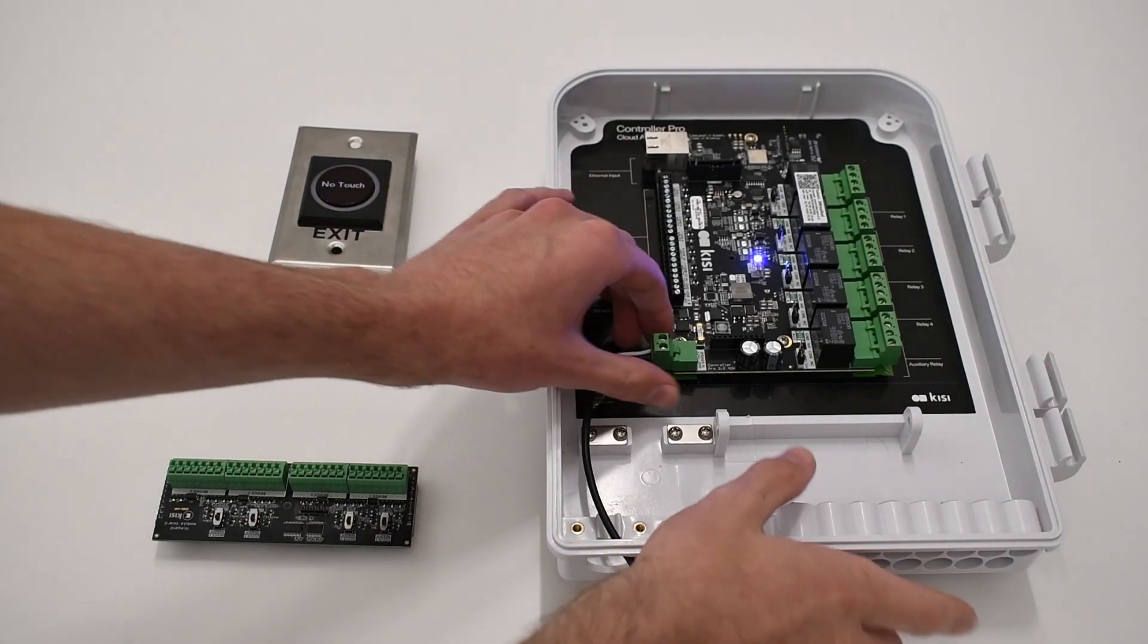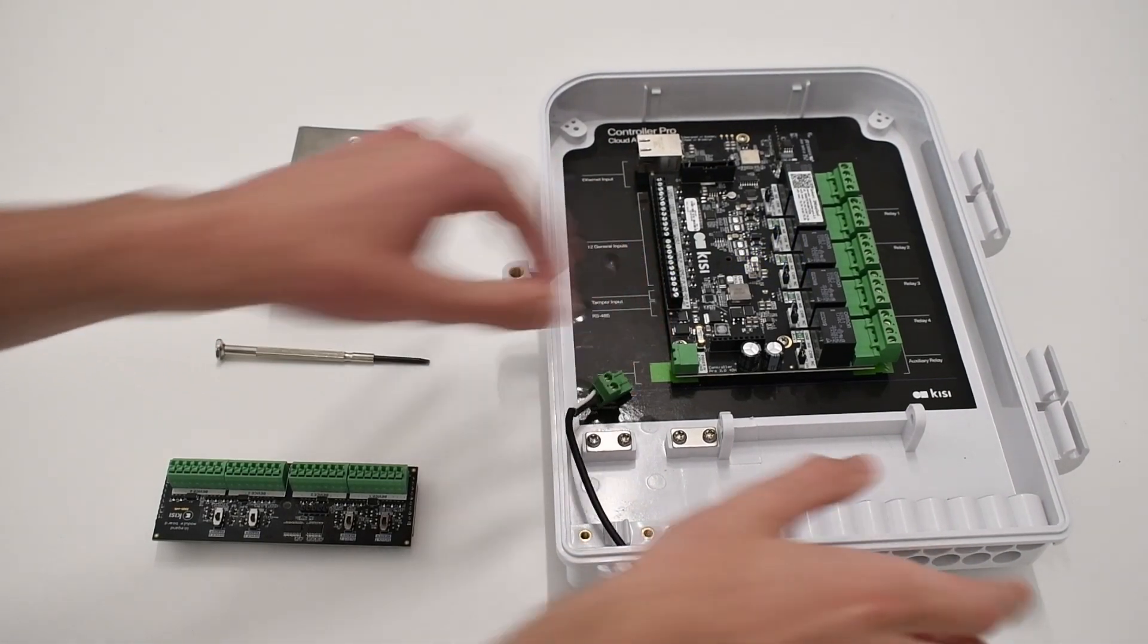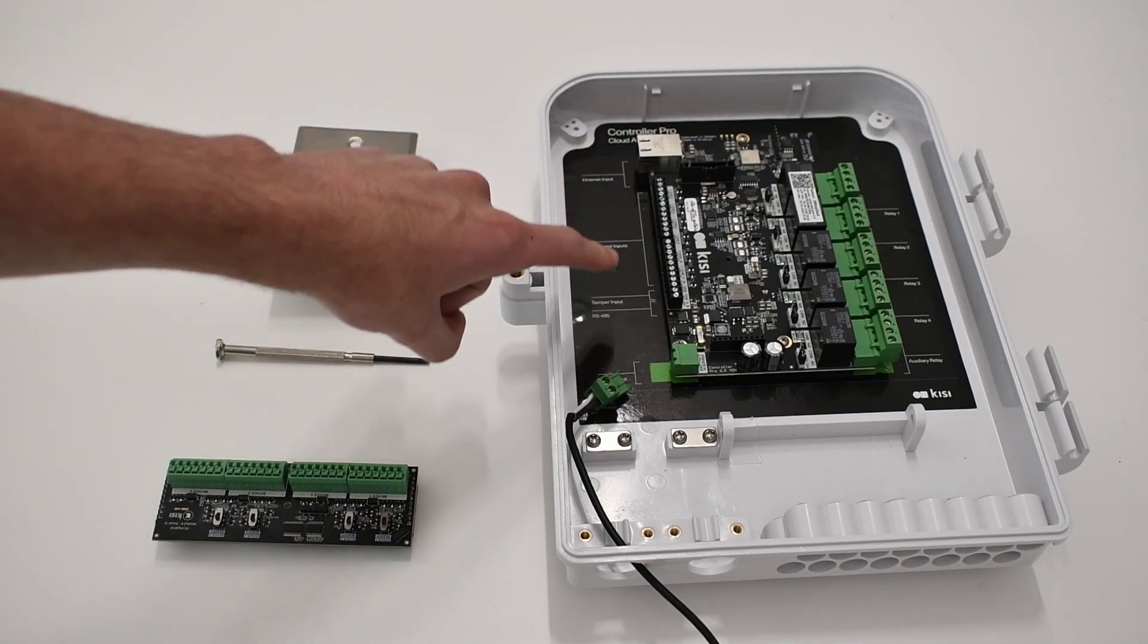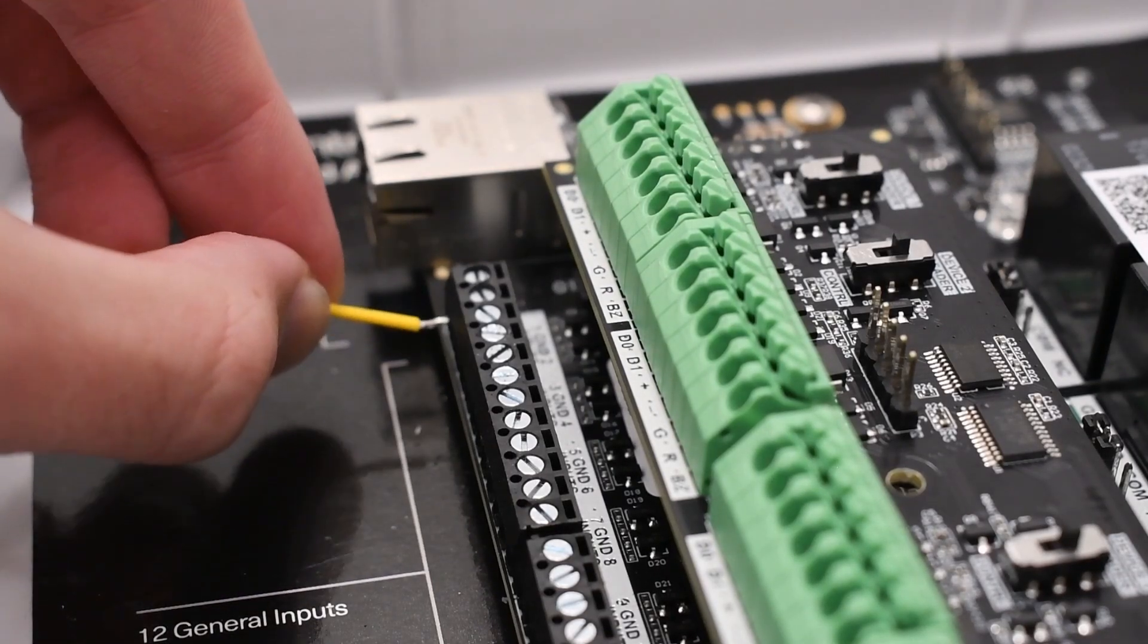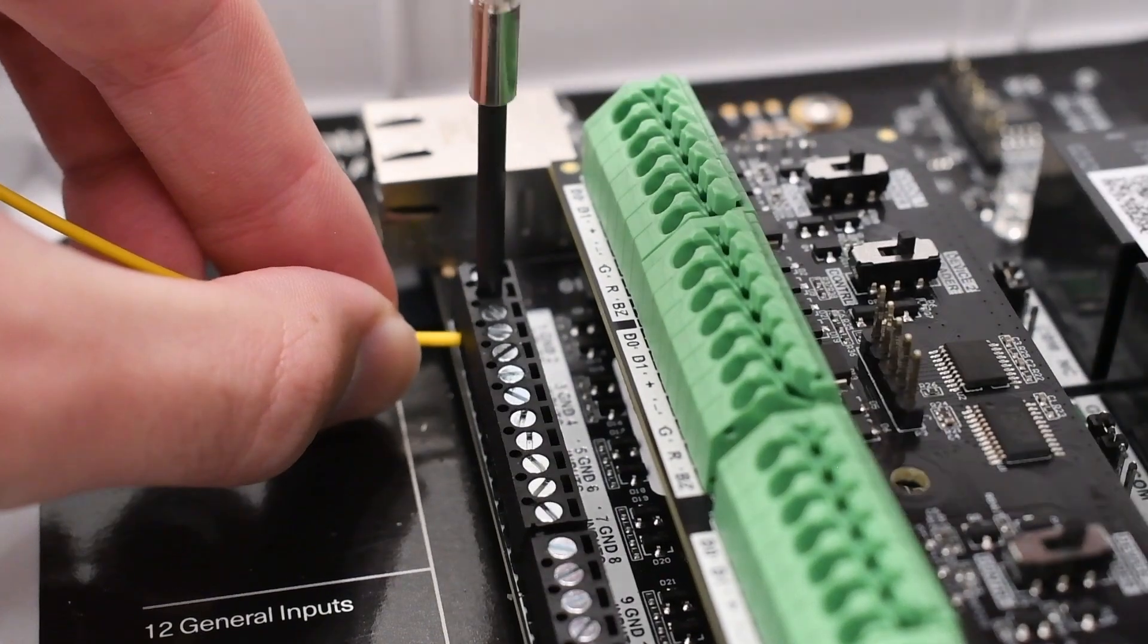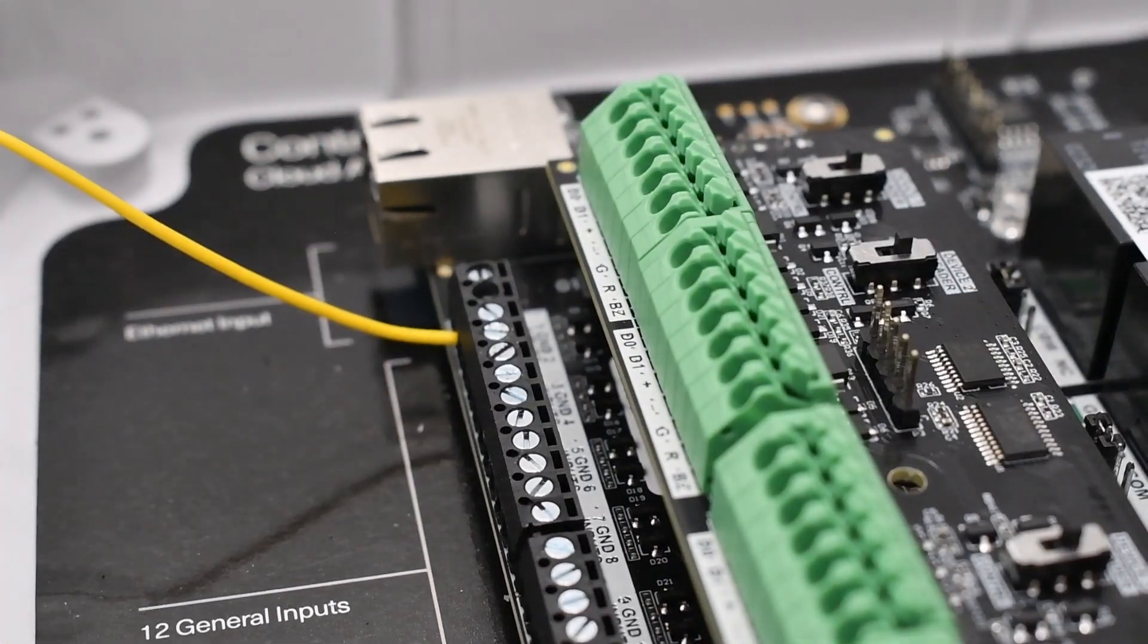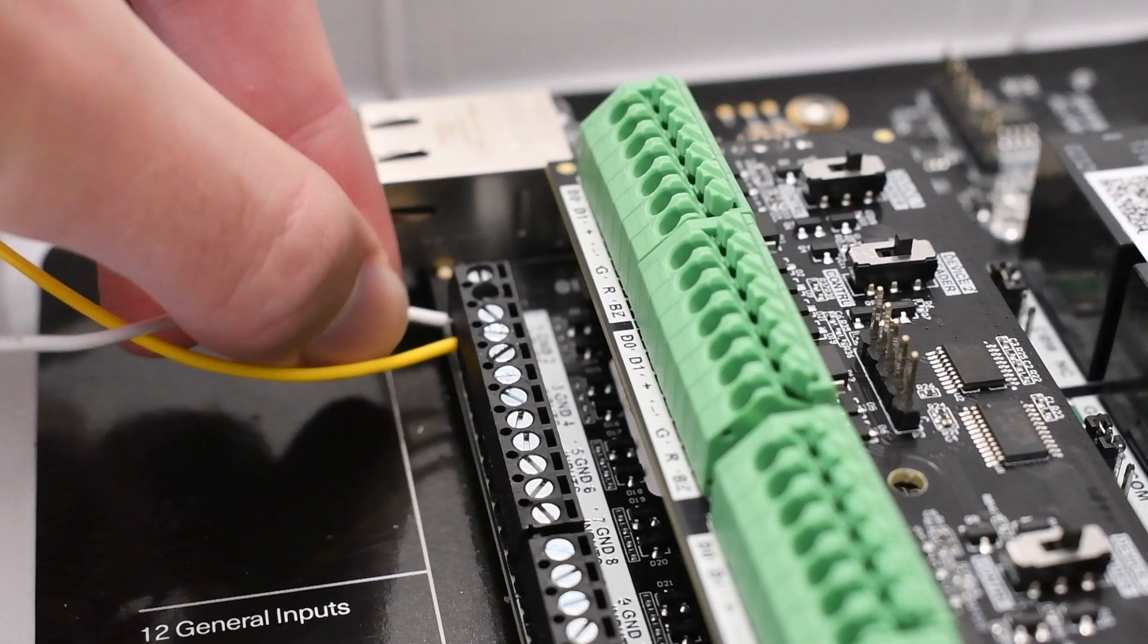Ensure the controller is unplugged and identify the general input pins on the left side of the Kisi Controller Pro 2. Now connect the COM output to one of the GND ports of the controller. Then connect the NC output to one of the numbered general input ports on the controller.